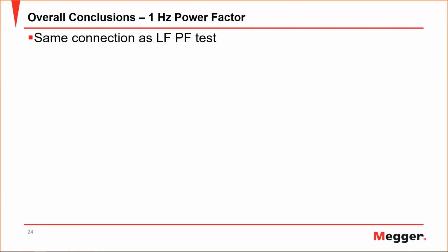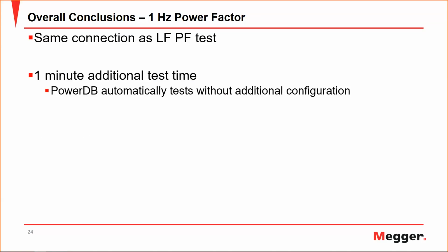Using the same connection as your line frequency power factor test and only 1 minute of additional test time, you can get more information about your asset. And what we've done in PowerDB is that we now automatically test at 1 hertz without any additional configuration needing to be done by the end user. So you open up the form, you select the asset that you're testing, and we are going to test it in the best way to give you the most complete information about the asset possible.